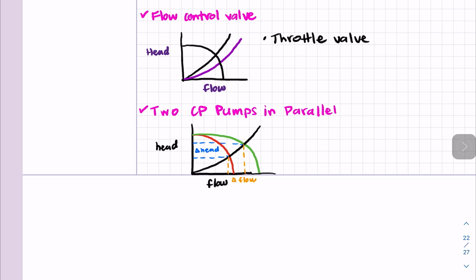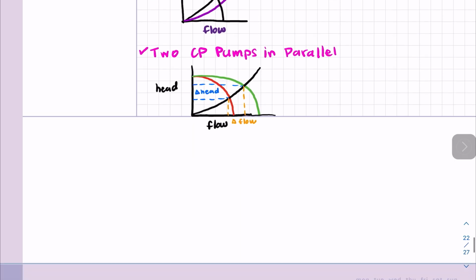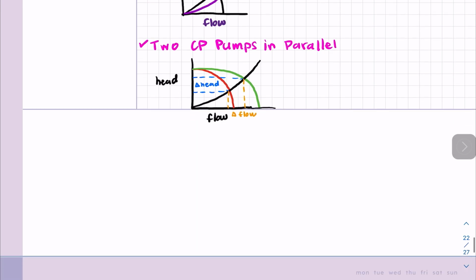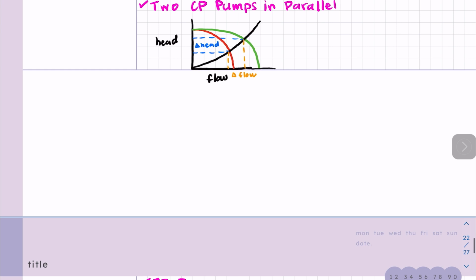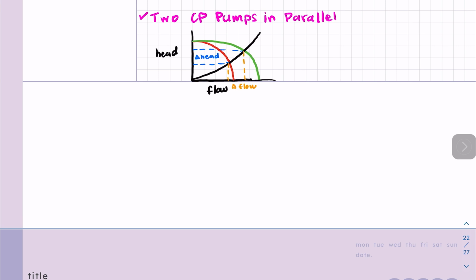Now we're going to have the final examples of the section. They are going to talk about pumps, right? If we have centrifugal pumps or positive displacement pumps in parallel or series, and what happens if we mix and match. So first, let's start with centrifugal pumps. We're going to see examples of operating them in parallel or in series, because when we do that, we are trying to achieve specific flow and pressure requirements for the piping system. That's the only reason why we start combining things.